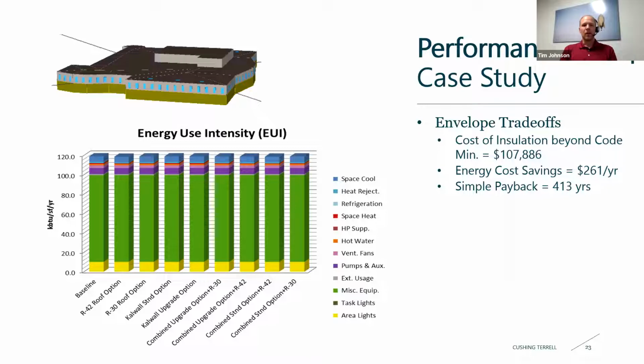So looking at, it was a major renovation of an existing facility. We found the cost of the insulation to add a couple inches of insulation was a little over $100,000, and the energy cost savings we get from it was about $260. So the simple payback is 413 years. So this is an example of a time maybe where we'd want to invest that extra money into HVAC systems or lighting upgrades or controls or that sort of thing.